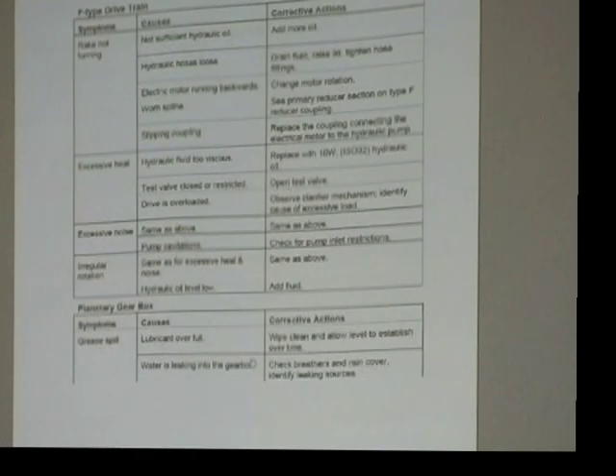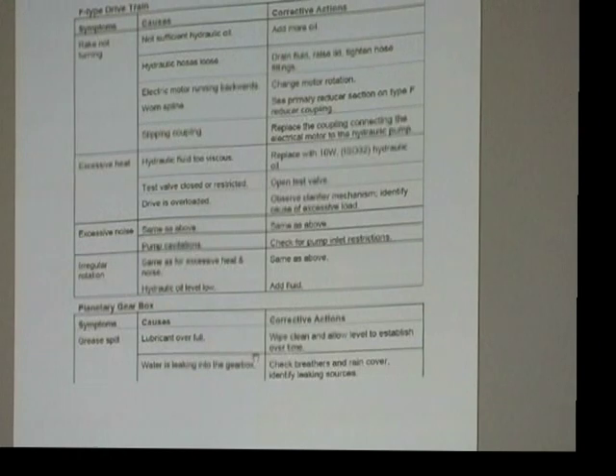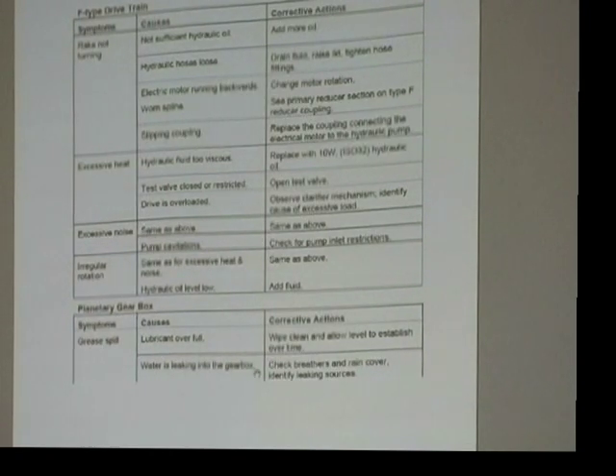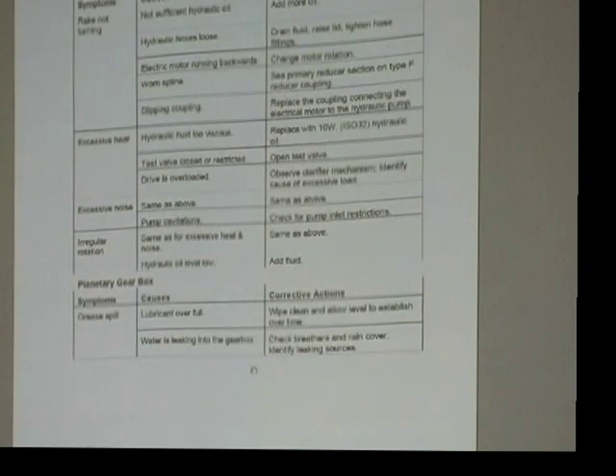It could be that the motor's running but the rakes aren't. And what would that be an indication of? The motor's still turning but the rakes aren't going anywhere. So the pressure relief valve's off. Yeah, but it's funny that it shouldn't have shut down. That means your switches need to be looked at too. If they haven't shut it off, then something in the system isn't shutting it down. But that's again your safety factor inside of there. We're going to initially set all those up anyways. Right, and we want to test them all, yep, make sure that everything's there.